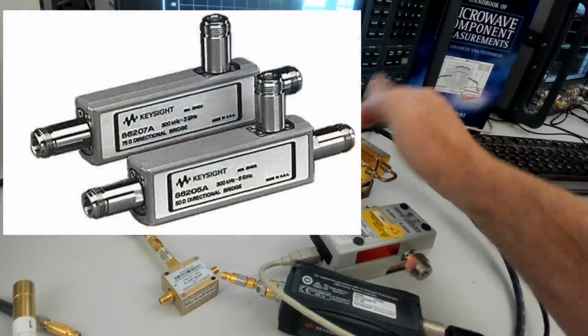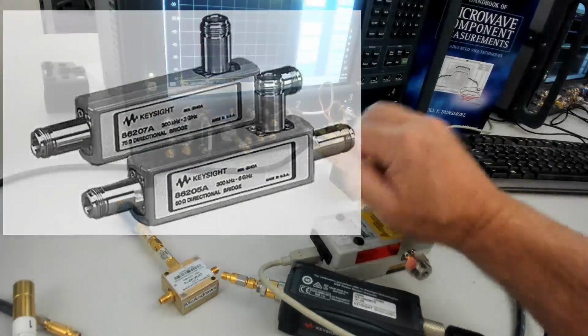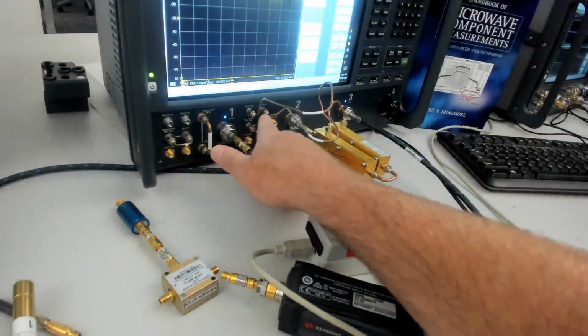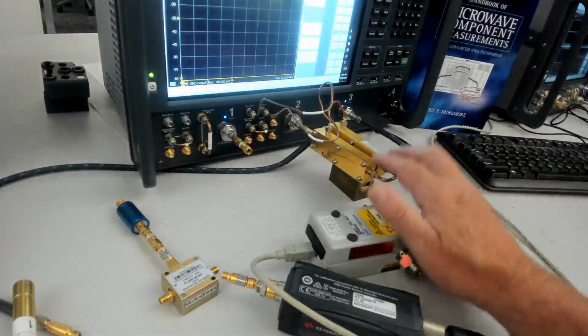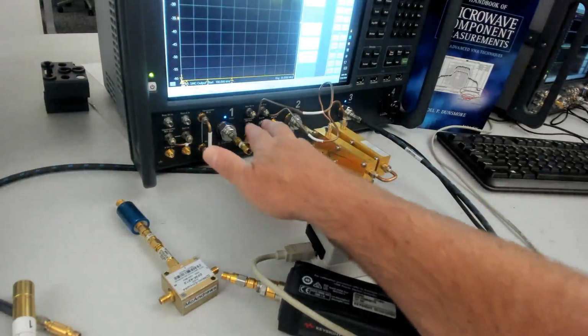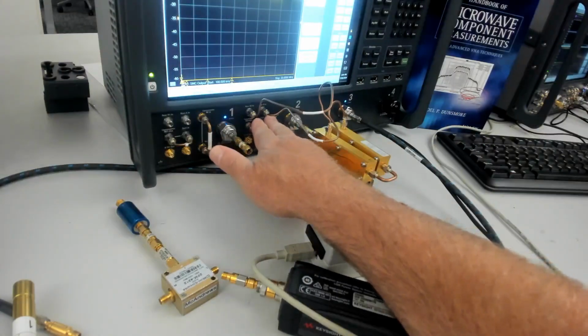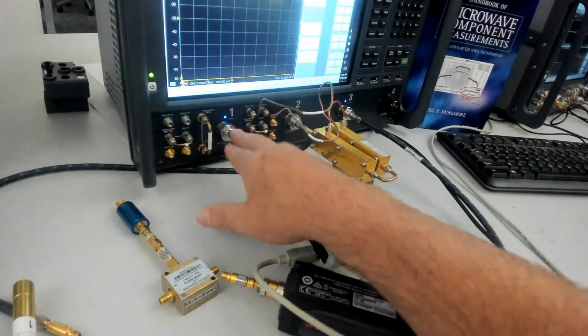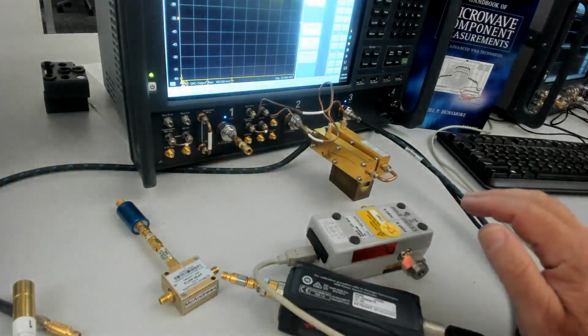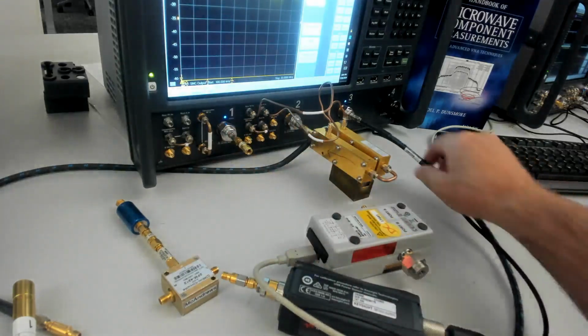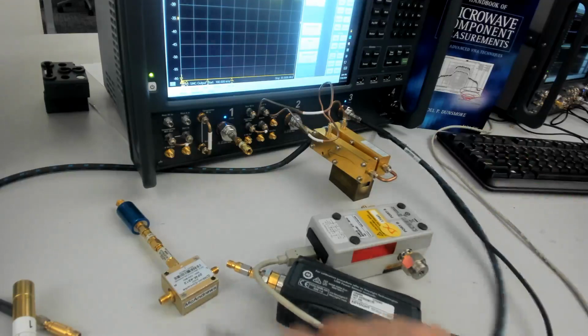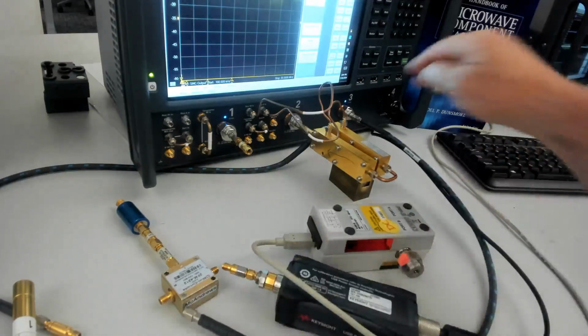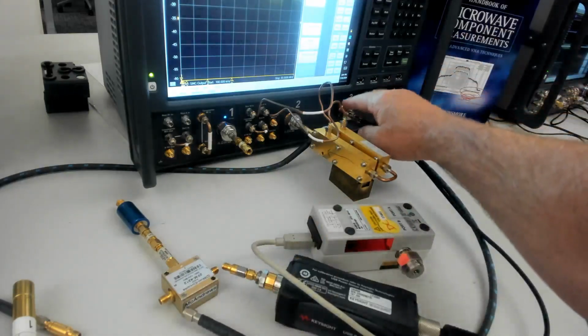This is connected for the reference coupler and the test coupler to the reference input and the test input on port 2. So external bridges using the external direct receiver access inputs here. Port 1 will be my RF port. It will be about 1565 megahertz, and then I'll use this cable here. Coming back over for the local oscillator, that's where I'll use the third port of the PNA-X.